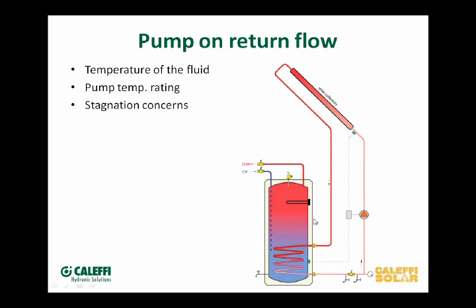We like to see the pump pumping up to the collector, because now it's in the coolest flow in the system. The hot water comes down from the collector, goes through your heat exchanger or the coil in your tank, and loses its heat there. By the time it gets to the pump, it's lost as much heat as it can exchange in the tank, so the pump runs at a much lower temperature. That was one issue — it has to do with the temperature the pumps can operate at.